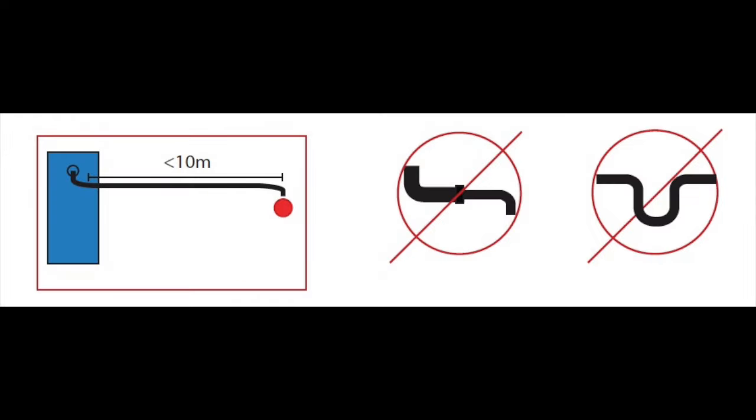The steam pipe must not go down and then up as this will create a trap which will block the steam from getting through.